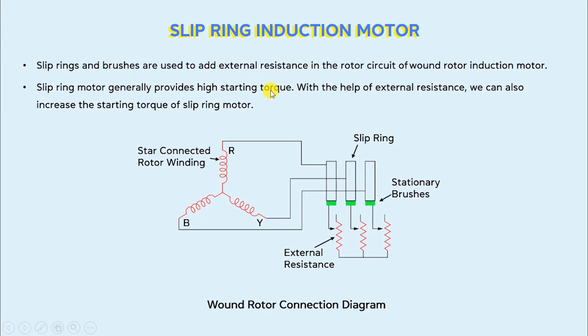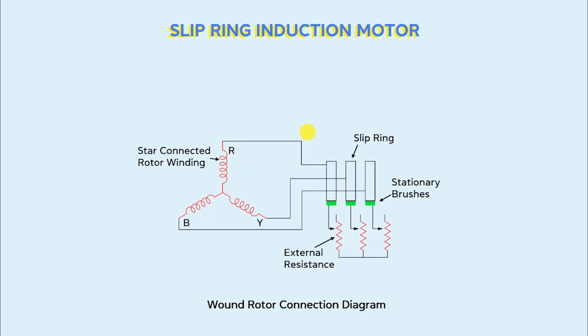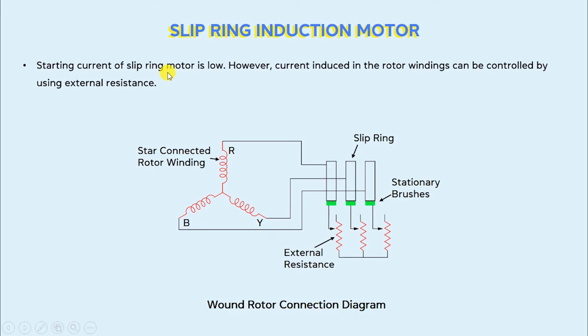A slip ring motor generally provides high starting torque. With the help of external resistance, we can also increase the starting torque of a slip ring motor. Moving forward, the starting current of a slip ring motor is low. However, current induced in the rotor windings can be controlled by using an external resistance. So one more advantage of external resistance is that the current induced in the rotor windings of a slip ring induction motor can be controlled.